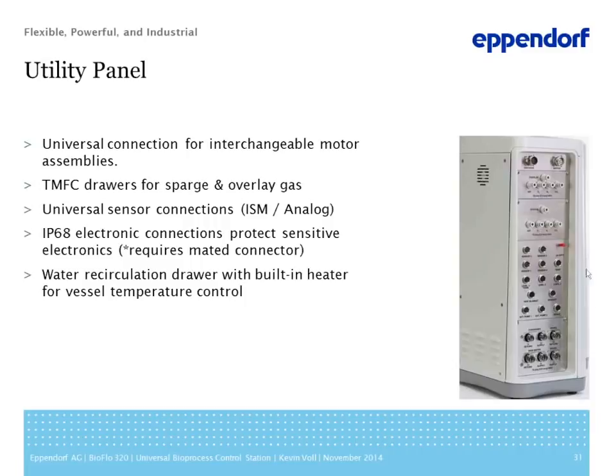And then we also have a water recirculation drawer, and this drawer on the bottom here is also designed the same as the sparge and overlay gas drawer, where 2 screws are removed and the entire water recirculation assembly, including the heater cartridge, can be removed. So this allows for a much more service friendly design and much more ease of installation. If there's an issue with that water recirculation drawer, the downtime is reduced because of this drawer design.